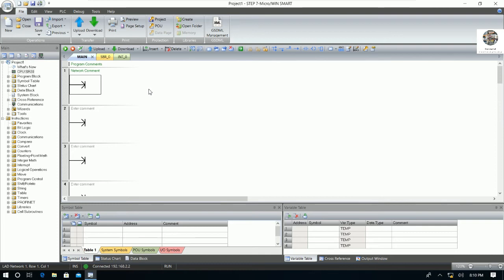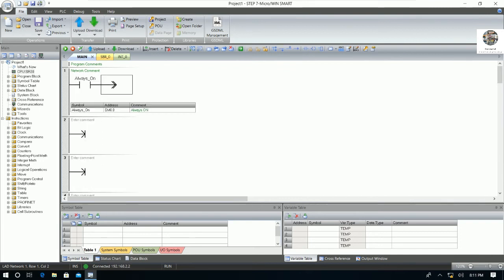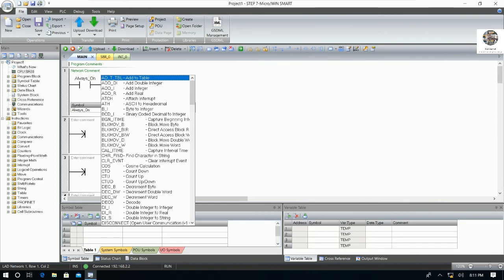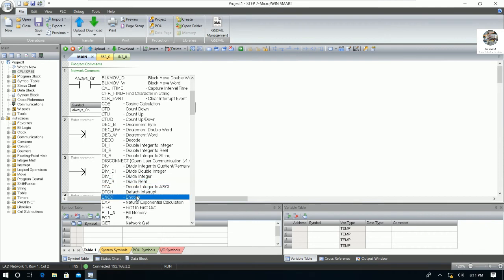Now we need to show the actual temperature for each channel, because I already connected the PT100 to channel number one and two of analog input EM0. To display the actual temperature, first we convert from integer to double integer, then convert to real, and then divide by 10. Use SM0.0 as the always-on contact. Go to Convert — integer to double integer.